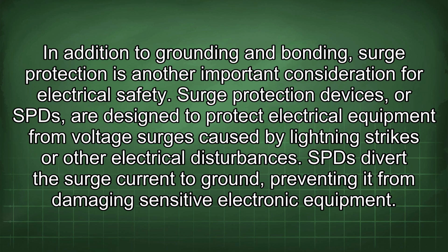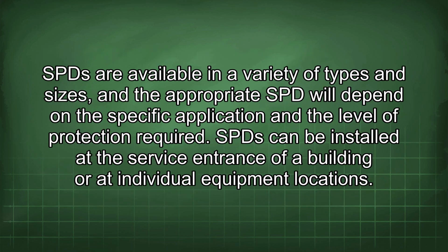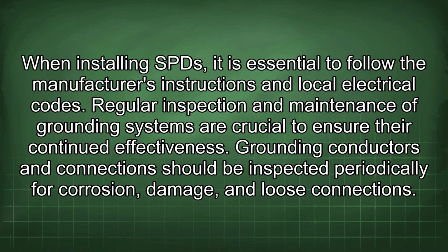Surge protection devices, or SPDs, are designed to protect electrical equipment from voltage surges caused by lightning strikes or other electrical disturbances. SPDs divert the surge current to ground, preventing it from damaging sensitive electronic equipment. SPDs are available in a variety of types and sizes, and the appropriate SPD will depend on the specific application and the level of protection required. SPDs can be installed at the service entrance of a building or at individual equipment locations. When installing SPDs, it is essential to follow the manufacturer's instructions and local electrical codes.